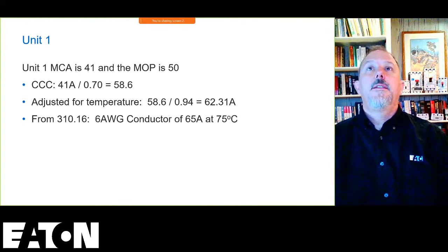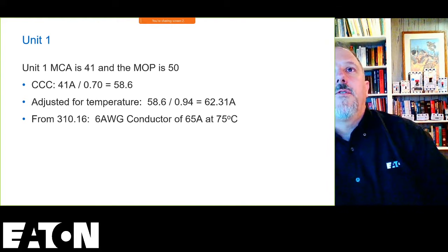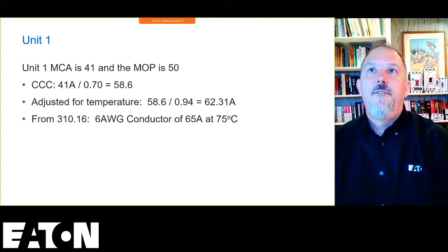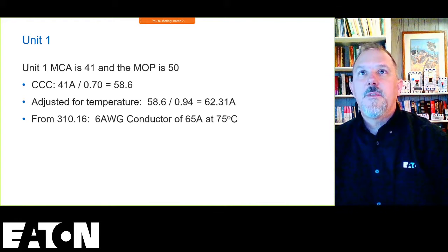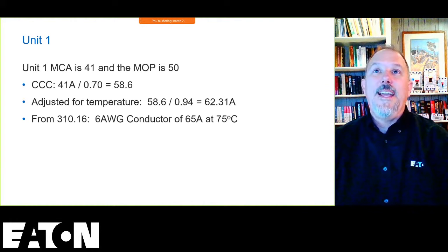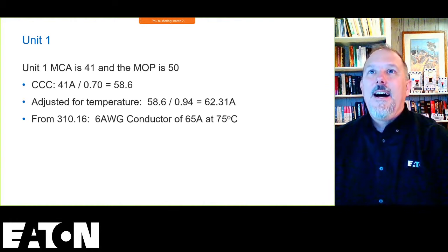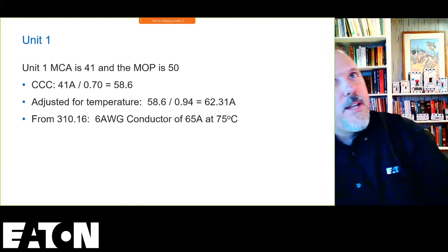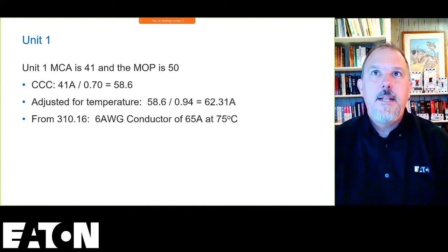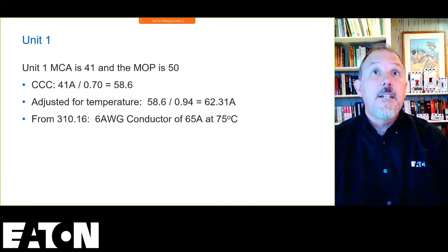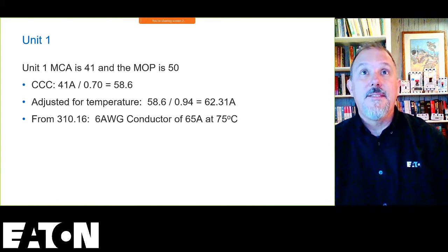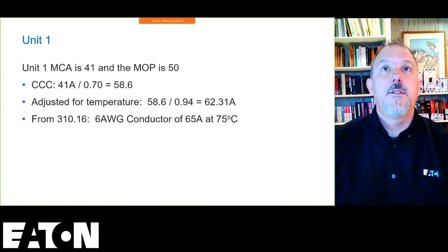Joe Andre says the NEC does not require an equipment ground. If the designer specifies the size of the EGC, follow that, or if he or she specifically calls out for it to be sized per 250.122 A and C, the table. So Mr. Andre is saying that because they're in a raceway, they don't need that equipment grounding conductor because it is in a metal conduit, I believe. Is that what you're saying?